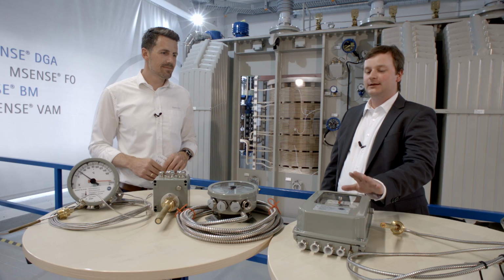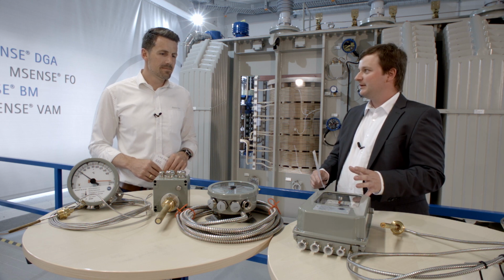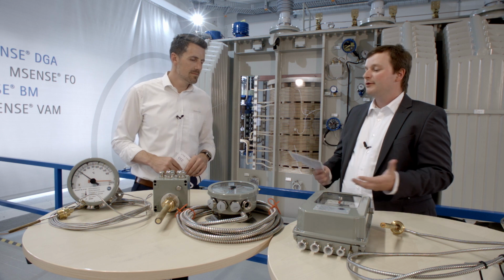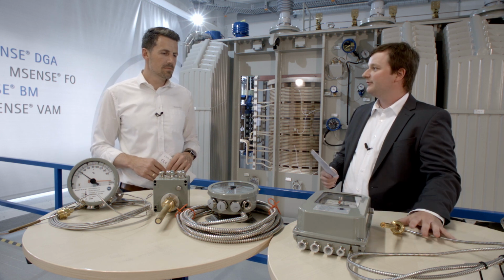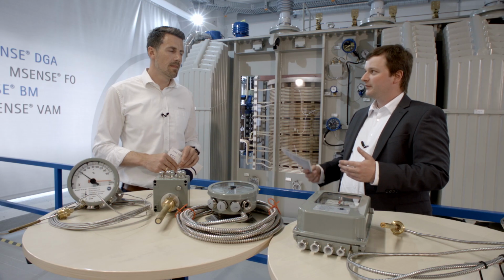On the left side, you see the MESSKO BTEC series using the bellow tube technology. It is a square-type thermometer, but the measuring system is more or less the same. It's also liquid-filled. The probe is sitting on top of the transformer, and once the liquid is expanding, then the bellows are moving, and with it the pointer of the thermometer itself. All three series of thermometers are available as OTI, which means oil temperature indicator, or WTI, winding temperature indicator. And this WTI is measuring and showing the thermal image of the transformer.